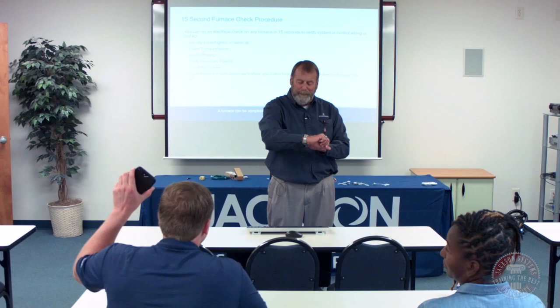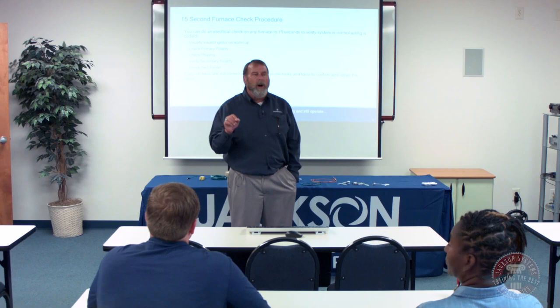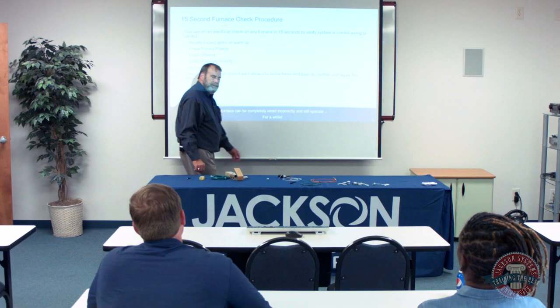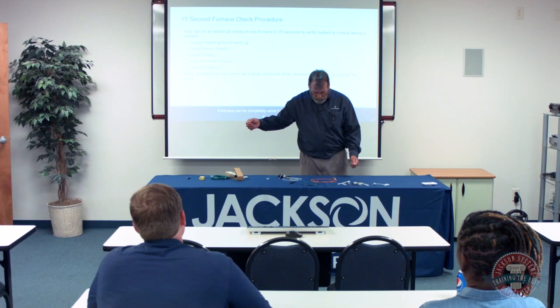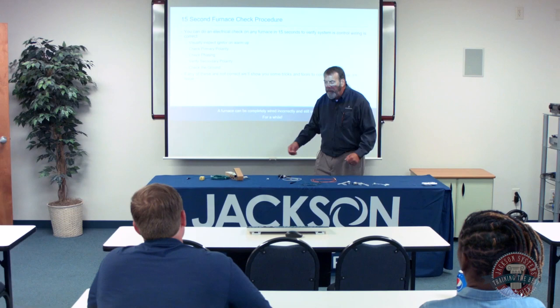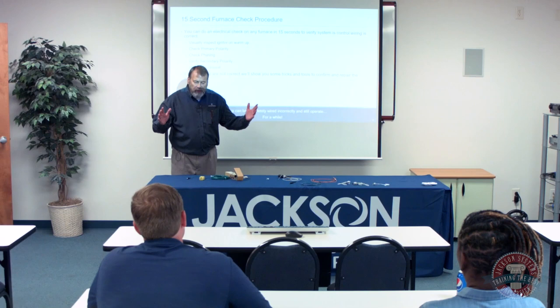When I say go, Matt, what I'm going to do is I'm going to verbally walk you through the steps, okay? I'll stand back here so the camera can pick it up. All right? Go. First thing I do is get out my cigarette and light it up. Take out my meter, 200 volt scale. L1, chassis ground. 120, primary is correct. TH, 98 volts. Phasing is correct. The igniter's glowing. Nope, don't see no hot spots. Ignition cool, done. How much?